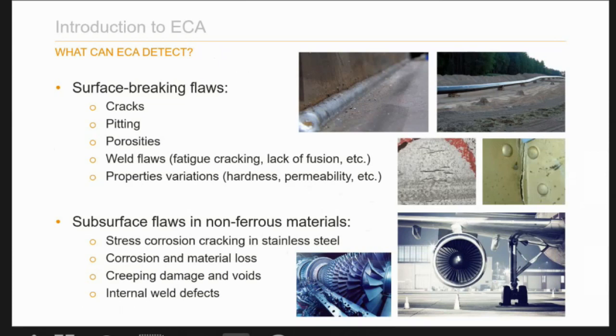Any surface breaking flaws, of course. So it can be a crack, can be pitting, porosities, well suited for weld inspection. You can also monitor property variations, so a difference in hardness, permeability or conductivity eventually. And when it comes to non-ferritic materials, you can also inspect and look for subsurface defects, and eventually far surface defects on thin material like stainless or aluminium, for example.